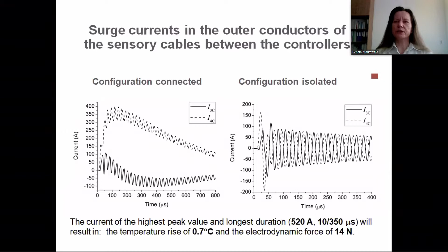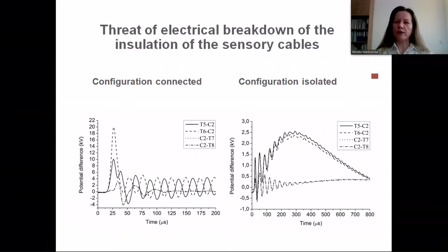For both configurations, the potential differences between the controller located nearest to the point of the lightning strike and terminators are very similar and close to the potential of this controller with respect to the remote ground. However, the potential differences between the controller located farther from the point of lightning strike and terminators are significantly dependent on the configurations, and this concerns both the peak value and the waveform.